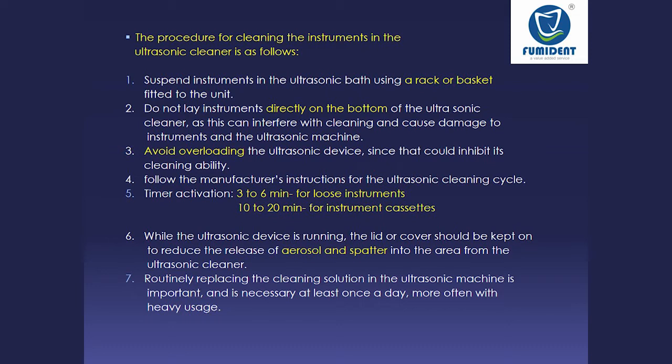Suspend instruments in the ultrasonic bath using a rack or basket. Suspend in the unit. Do not lay instruments directly at the bottom of the ultrasonic cleaner. This is because it will interfere with the cleaning procedure. Again, avoid overloading of the ultrasonic cleaner, as that could inhibit its cleaning ability, and routinely change the ultrasonic cleaner solution at least once in a day or more often with heavy use.